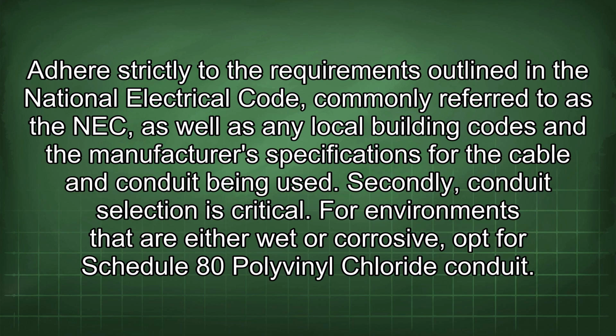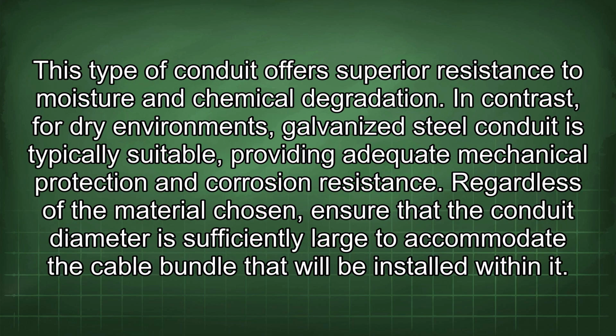Secondly, conduit selection is critical. For environments that are either wet or corrosive, opt for Schedule 80 polyvinyl chloride conduit. This type of conduit offers superior resistance to moisture and chemical degradation. In contrast, for dry environments, galvanized steel conduit is typically suitable, providing adequate mechanical protection and corrosion resistance.